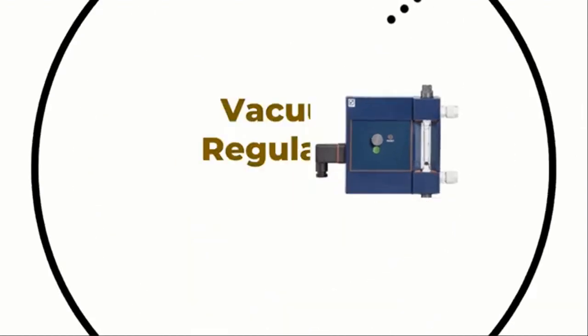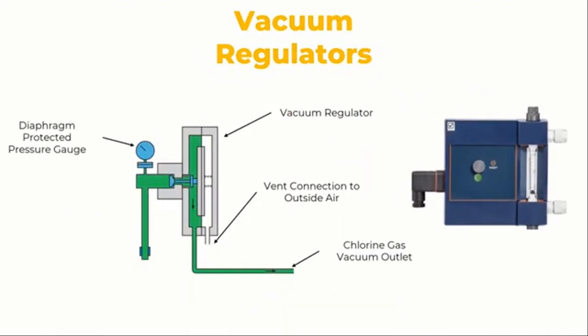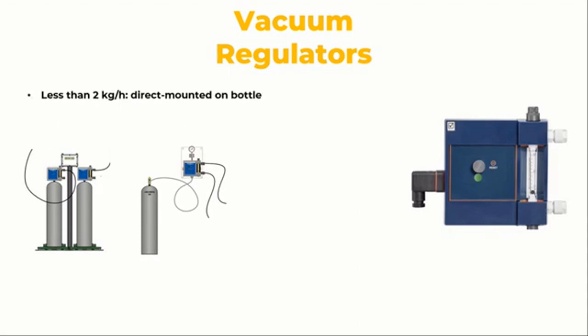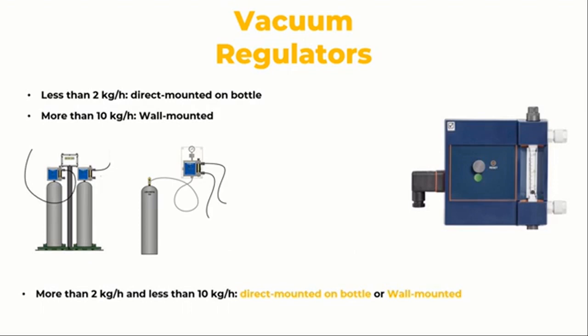The vacuum regulator unit keeps the chlorination under constant vacuum. To reduce the length of pressurized chlorine pipe, it should be placed as near as feasible to the chlorine supply container. It may be mounted on the wall or the cylinder. The type of mounting for the chlorometer is determined by the maximum chlorine flow rate required. It should be directly installed to the bottle for flow rates under 2 kg per hour, and wall mounted for speeds more than 10 kg per hour. It can also be directly fixed on a bottle or wall mounted for flow rates greater than 2 kg per hour and less than 10 kg per hour.